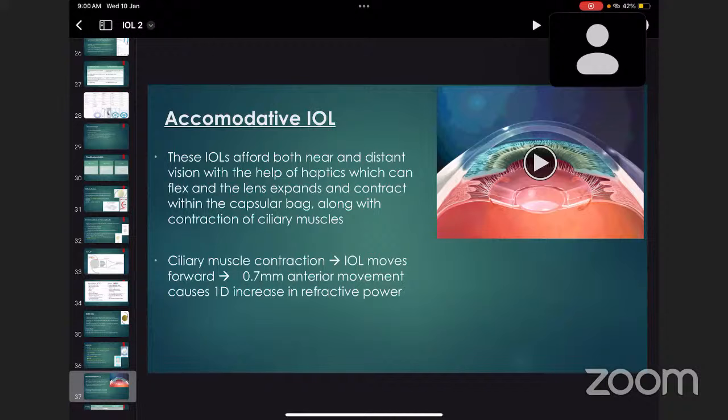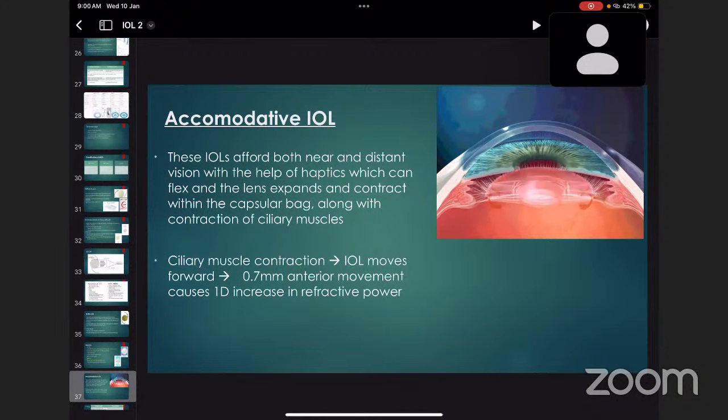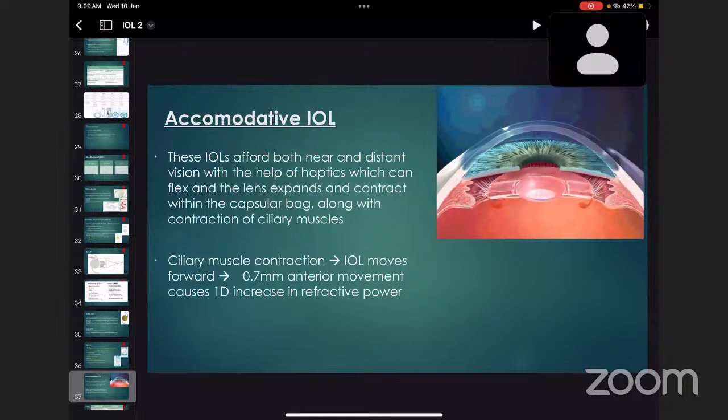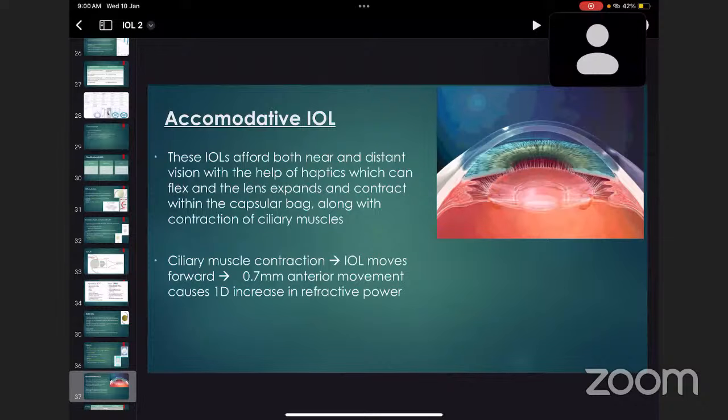Accommodative IOLs: these IOLs afford both near and distance vision with the help of haptics which can flex. As we can see in the image, it flexes and the lens expands and contracts within the capsular bag along with contraction of ciliary muscles. Whenever there is ciliary muscle contraction, IOL moves forward. There's 0.7 mm anterior movement which causes one diopter increase in refractive power.